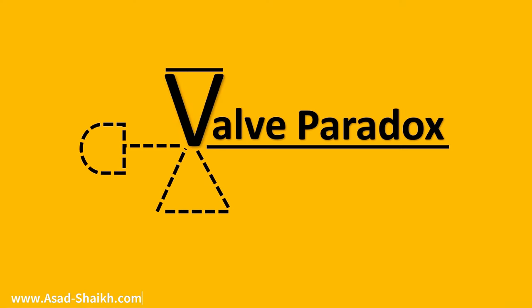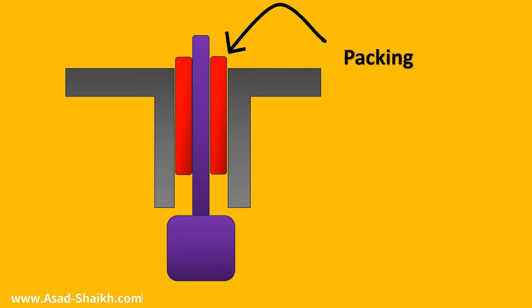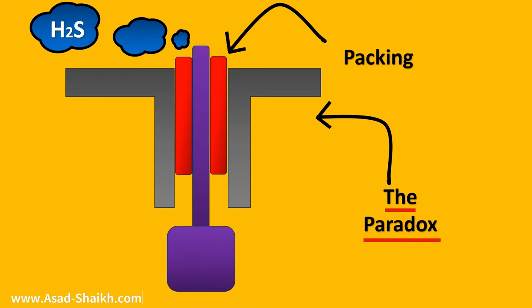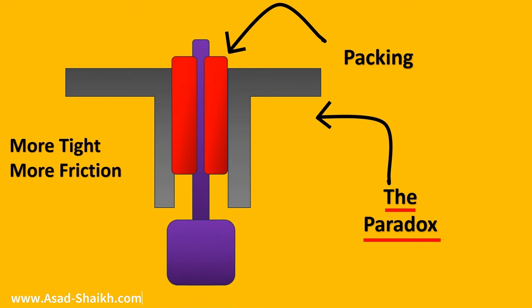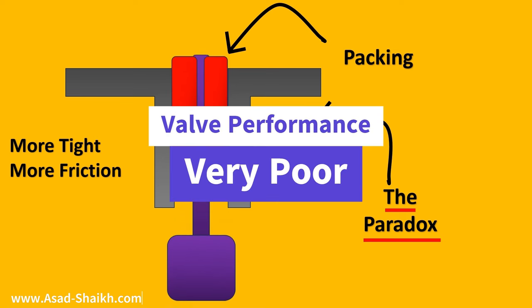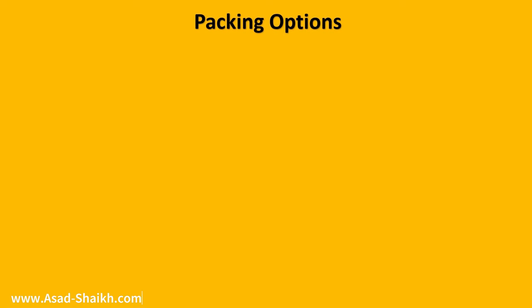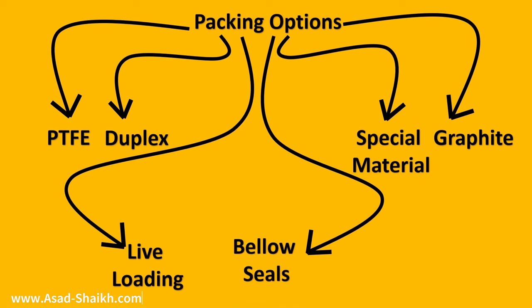Finally, there is something very important called the valve paradox. Looking at a control valve, you can see the bonnet and the packing shown in red. The valve paradox occurs when the control valve is working and regulating flow dynamically. When fugitive emissions happen and you decide to make the packing tighter, emissions reduce — but the tighter packing creates more friction, causing the valve to function with very low performance. However, if you reduce the packing to improve performance, fugitive emissions increase again. Engineers had to develop creative solutions, leading to dynamic packing options: duplex packing, special materials, special V designs, live loading, and bellow seals.